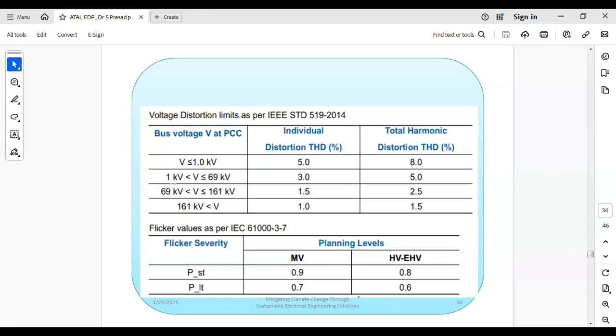And when your point of interconnection is 1 kV to 69 kV, the individual harmonics, starting from the second order to the 50th order, have to be less than 3%. When you calculate the total harmonic distortion at the point of interconnection, it has to be less than 5%. You have to take care, and this will be verified, whether you satisfy all the conditions of the CEA regulations or not.